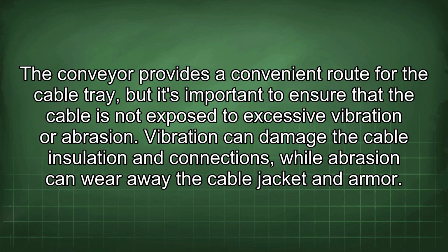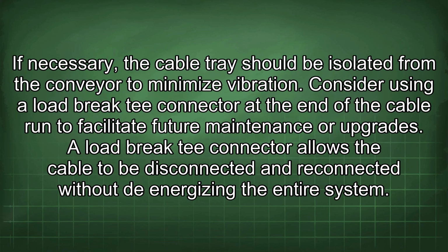The conveyor provides a convenient route for the cable tray, but it's important to ensure that the cable is not exposed to excessive vibration or abrasion. Vibration can damage the cable insulation and connections, while abrasion can wear away the cable jacket and armor. If necessary, the cable tray should be isolated from the conveyor to minimize vibration.